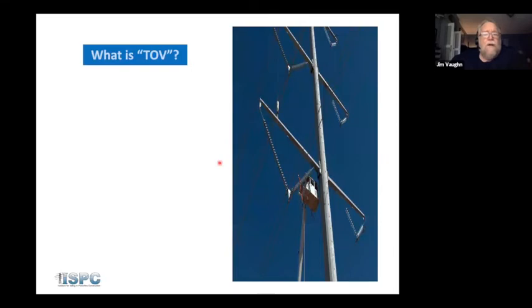So what is TOV? Okay, now first of all, disregard the grounds. I use this picture here because it kind of shows where TOV catches you off guard. You may find yourself very, very comfortable working in this position on an energized circuit. I hope not, because this is a bad place to be. But what these guys are actually doing is replacing bad brackets on these arms, and that's why they're where they're at. They are not there in an energized location.